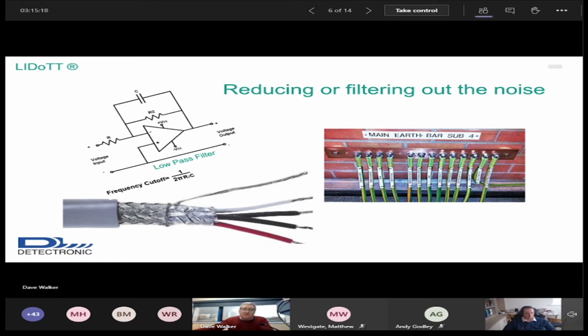There's a lot of research done on earth bonding. If anybody's experiencing problems with noise on instrumentation, mains powered instrumentation, then there's a lot of research being done on how to make sure you've got a decent earth bond. There's been a change in switchgear over the past 15, 20 years to make it more efficient. The knock-on effect is we get high voltage spikes when it switches on and off, or changes its phase. So the earth supplies now have got to be much more robust than they ever were previously.